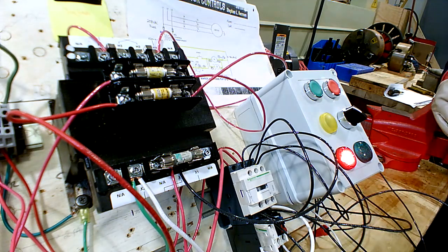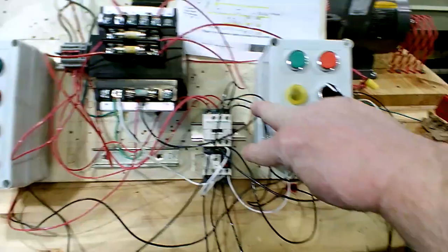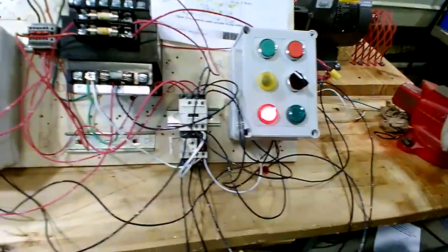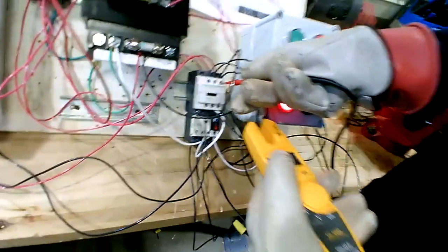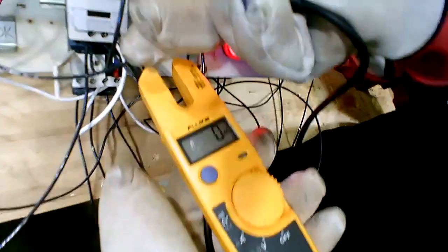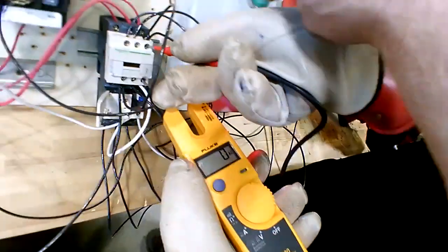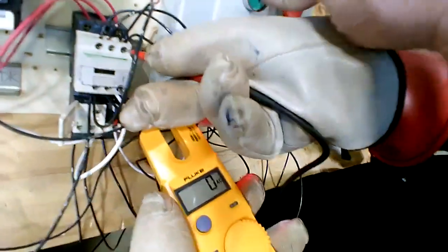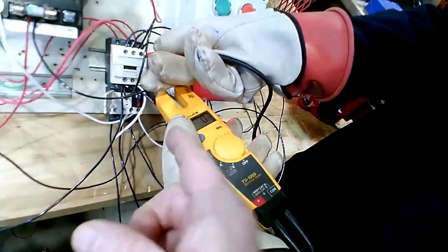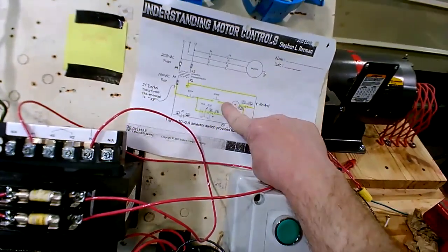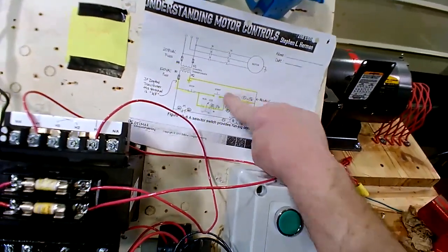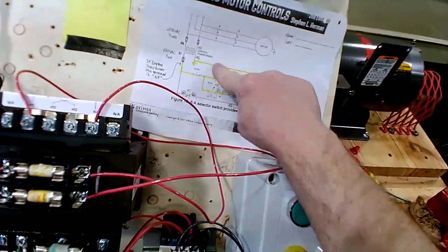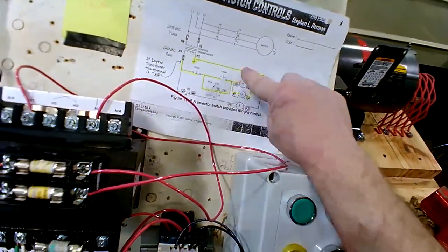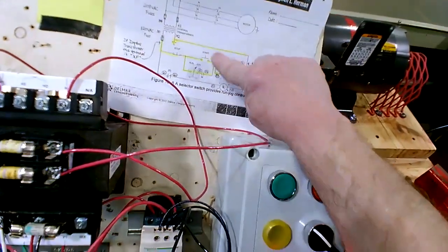So when you measure across the coil right now, what it actually tripped, go ahead and put your meter across it. And you're getting nothing there, right? When I press the button, you see nothing, right? Now watch on the schematic. I want you to move with your meter, instead of checking from A1 to A2, check from A1 to 96 beyond the overload, and you'll be able to get a reading there. Because you've actually got a neutral uninterrupted out here. If you get on real neutral beyond that break point, you'll be able to read that signal.